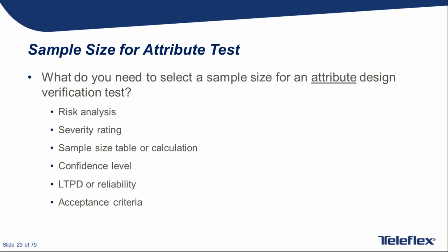As we have seen, attributes are simpler. We start with the risk analysis and get the severity rating of the situation that the testing is related to. Then, as you will see, we can refer to just one table for the sample size. So start with risk, get into statistical tables, do the testing, apply the acceptance criteria, and make decisions about whether the testing passes or fails.